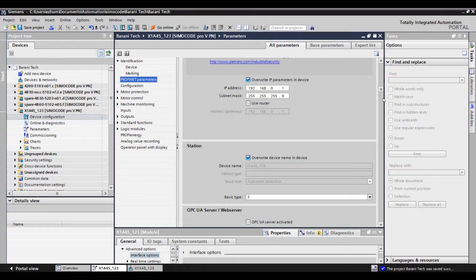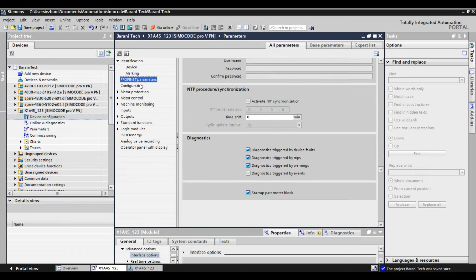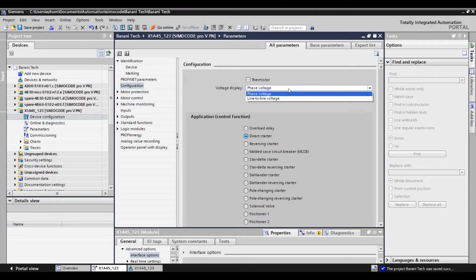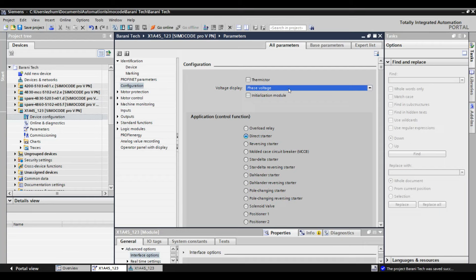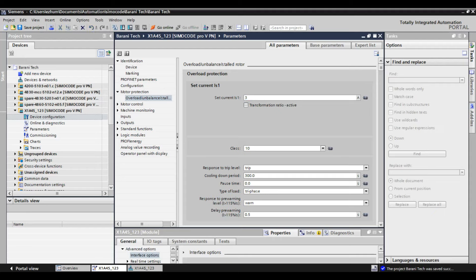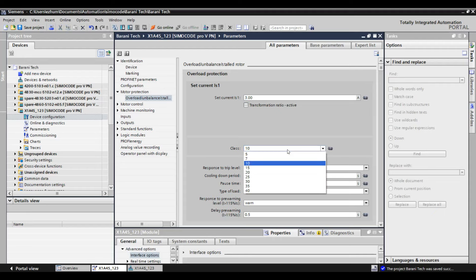Now I am going for parameter settings. Here I am selecting the voltage selection, and it is also possible to change the type of starter here. Now I am going for protection settings. Here you can see IS1 — this is the motor full load current. For example, if your motor full load is 49 amps, then you have to put 49 amps. The next very important selection is the motor thermal class.